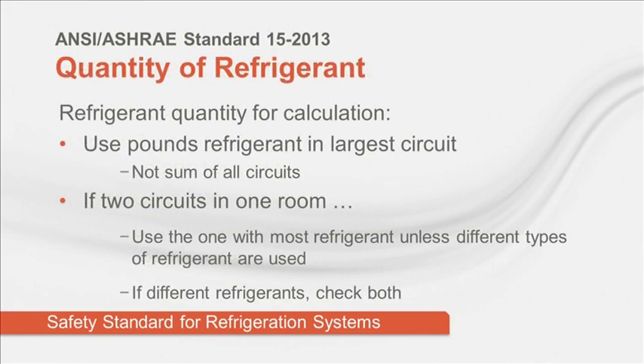Standard 15 considers the entire charge in the circuit serving the coil to be the amount that will discharge due to a failure. If the room contains distinct, independent refrigeration circuits, use the refrigerant quantity in the largest circuit, not the sum of the refrigerant in all circuits. This is mainly important where parts of more than one refrigeration system share the same dilution volume. For example, if you have a room served by 1 VRF system, but the refrigerant piping from a second system passes over the room, the one with the larger charge should be used to determine compliance with the RCL. If the systems contain different types of refrigerant, both should be checked for compliance.